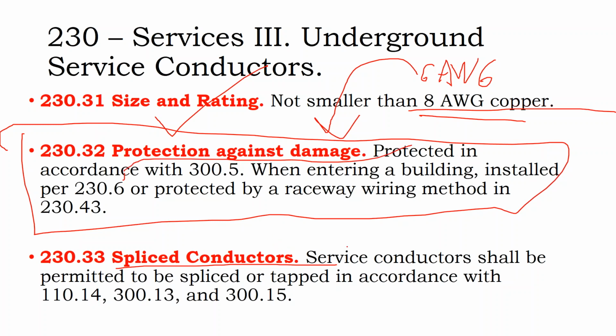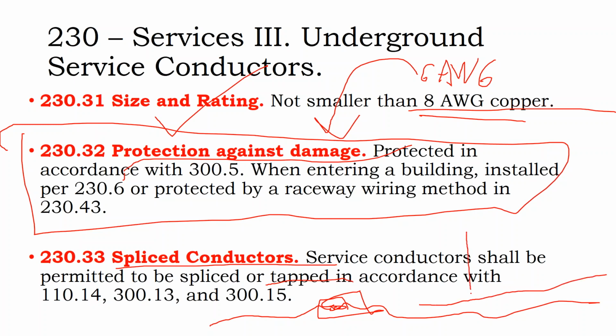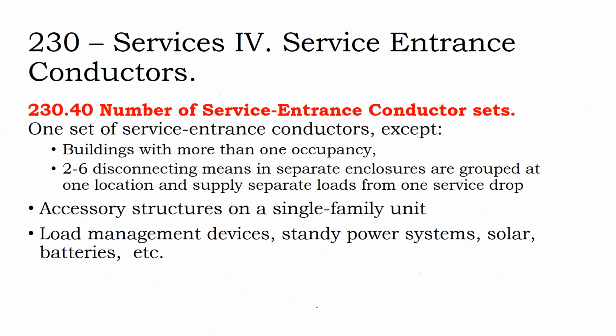We're getting into conductor splicing, and splicing is when you take one conductor and you're out of length on your conductor, and then the conductor is supposed to pick up, and you install a little junction box and you splice them onto each other. So you're allowed to splice conductors in most cases, or it says tapped. Tapping is where you might have one line and you want to install another line, and you connect them all up inside a junction box, and that would be a tap rather than a splice. It says you can have spliced conductors in accordance with certain rules, and these are rules that apply to Section 300 wiring, so we'll see those rules pop up.